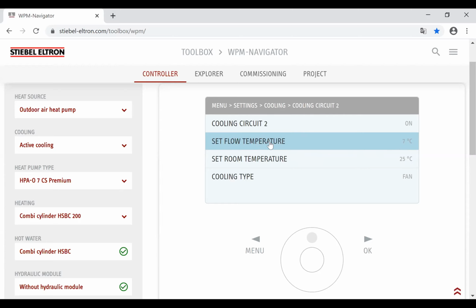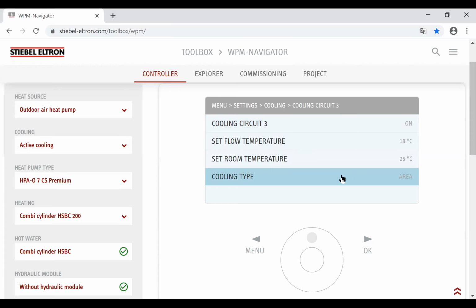So we can set the fan coil units, being our cooling circuit 2, to fan coil mode. Let's go back one. Circuit 3 may be our underfloor area. So cooling type, we want area cooling. So as soon as you put on area cooling, all of a sudden that cooling circuit will enter dew point management mode. Okay, you don't have to set anything else for that. That's the function that it's in, dew point manage mode. So you can change, cooling circuit by cooling circuit, which mode that circuit is in.